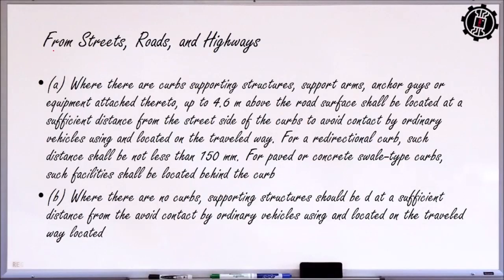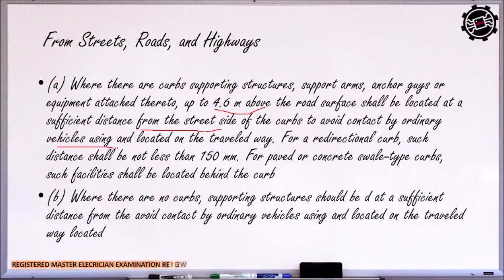Okay. So from street, roads, and highways. Where there are curbs, supporting structures, support arms, anchor guys, or equipment attached thereto, up to 4.6 meters above the road surface shall be located at a sufficient distance from the street sides and the curbs to avoid contact by ordinary vehicles using and located in the travelway. So 4.6 meters yung minimum clearance. This is for the supporting structures. For redirectional curb, such distance shall not be less than 150 mm, no? So yung horizontal niya dapat hindi bababa sa 150 mm.